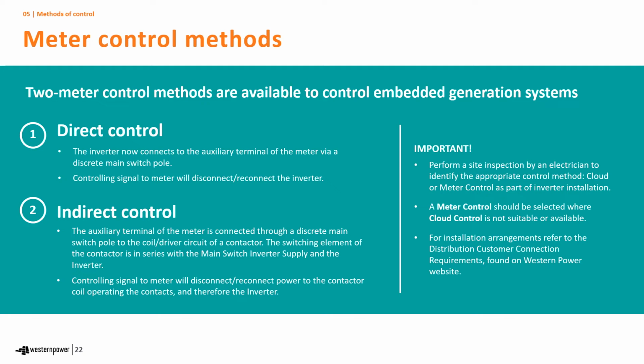The second method for meter control is indirect control. In this method, the same mechanism is used, but it's connected through a discrete main switch pole to a coil or driver circuit of a contactor. The switching element of the contactor is in series with the main switch inverter supply and the inverter. When we send the controlling signal to the meter to disconnect or reconnect power to the contactor, the contacts open or close, and therefore so does the inverter.